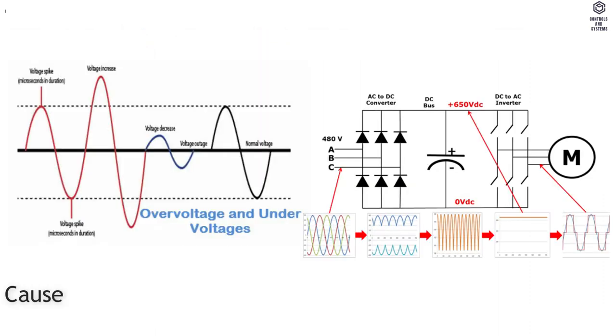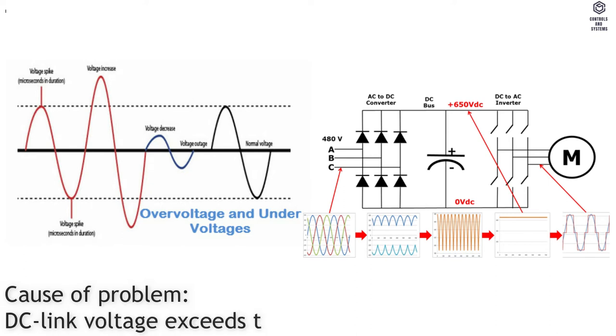Warning and Alarm 7: DC Overvoltage. Cause of Problem — DC link voltage exceeds the limit.